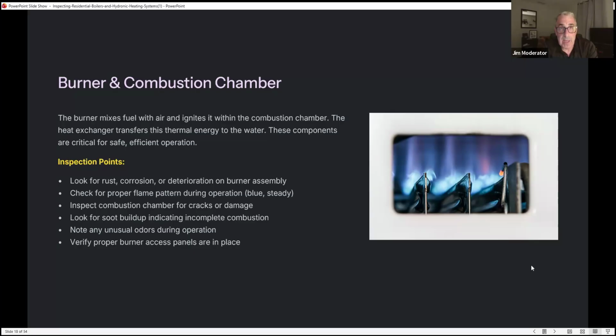That's going to be hard in a lot of systems. Some of the older systems have little view chambers that you can move to see in there. Look for soot buildup indicating incomplete combustion. Note any unusual odors during the inspection and verify proper burner access panels are in place.